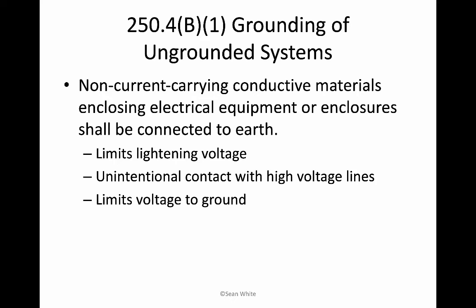If you did have a factory that had 480 delta ungrounded and then there was a ground fault, the factory could still keep running, because the ground fault would just make the system grounded temporarily while there is a ground fault. That is just some things that could potentially happen. Some of the different reasons that we do grounding are limiting of lightning voltages and unintentional contact with high voltage lines. So a high voltage line goes and hits something, we want everything to be bonded and grounded together. And also we would limit our voltage to ground. Those are different reasons why we ground these systems, even when they're ungrounded.